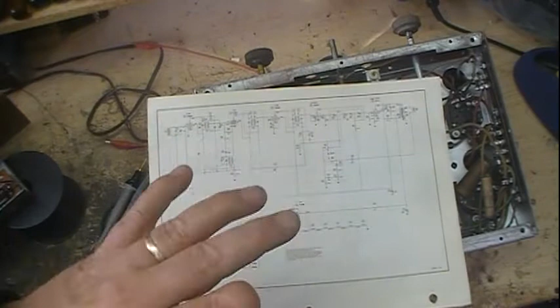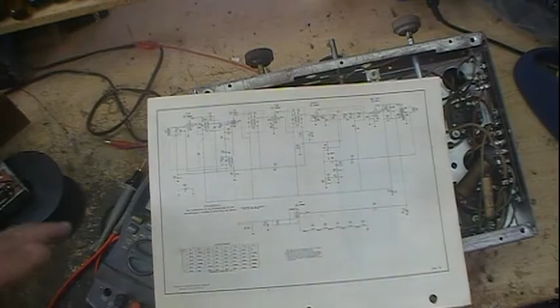But basically all your DC voltages, unless otherwise stated, will be referenced off of ground. So in other words, your negative lead, common lead off your meter will connect to ground, and the only thing you'll have to do is locate that ground. Transformer sets generally will be chassis, so the actual metal chassis, so just pick a good spot where you can get a good connection. Use a gator clip test lead, that way you don't have to keep it held there, and you keep both hands away from the chassis. Use only one hand for measuring.